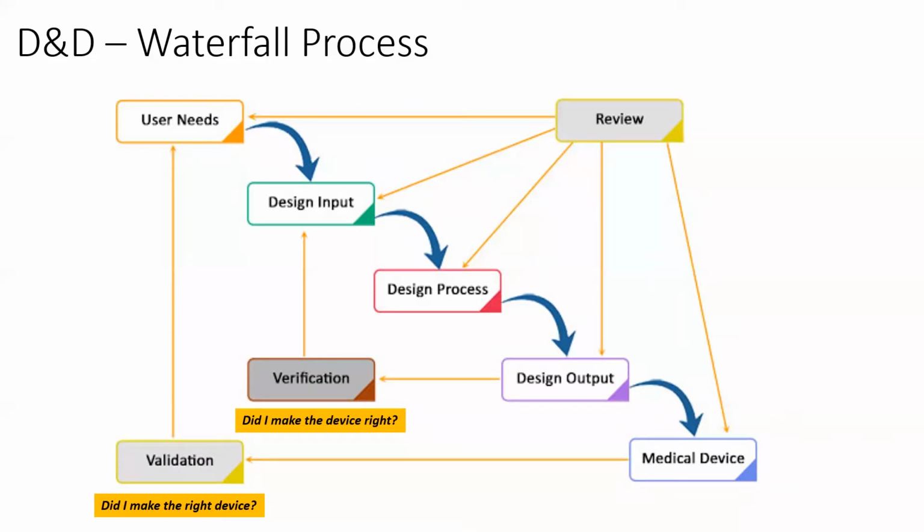And a very good way of understanding the difference between verification and validation is verification checks, did I make the device right? That means, is my design output in accordance with my design input? So there's no mistake anywhere. Okay. Whereas validation is a little different.